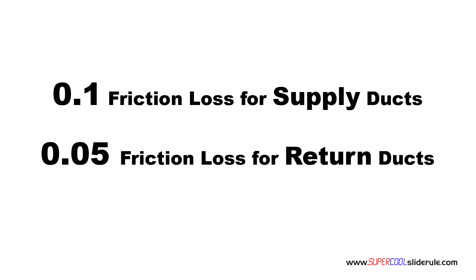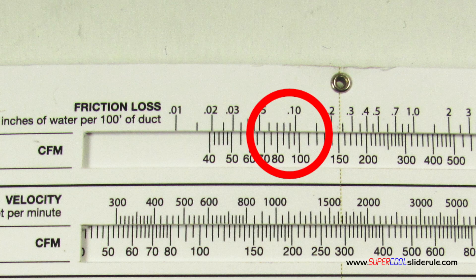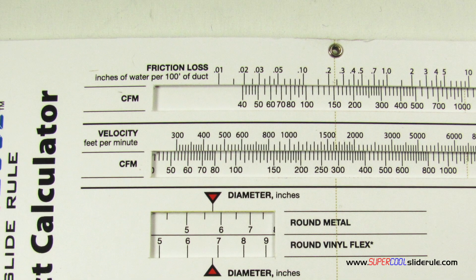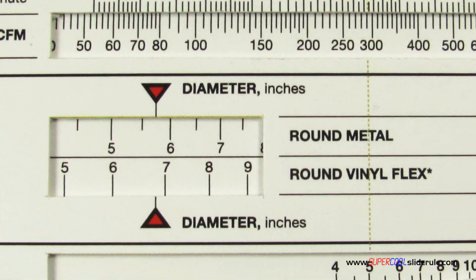We use .1 for all supply ductwork and .05 for all return air ducts. Indexing 96 under the .1 looks just like this. Next, we reference the flexible duct window and note that the closest duct size is 7 inch. When between two duct sizes, as shown here, always choose the larger size. Repeat this process for all supply ducts.